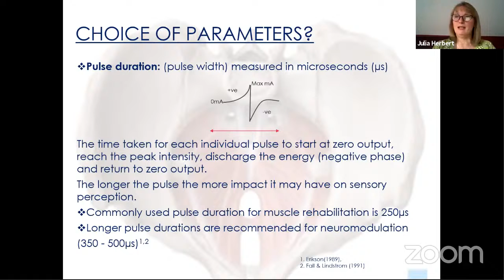The longer the pulse, the more impact it may have on the sensory nerves, because we're not just getting the motor nerves that we want, we're going to affect the sensation in that area. So the commonly used pulse duration for muscle rehabilitation is about 250 microseconds, but a lot of the papers that have been done for neuromodulation using vaginal or anal probes actually will use a longer pulse duration to have more stimulus on the sensory feedback mechanism back into that neuromodulation to the bladder.